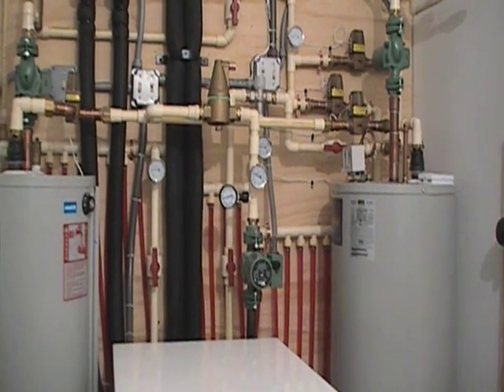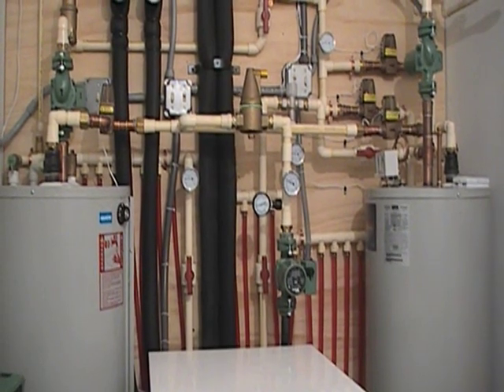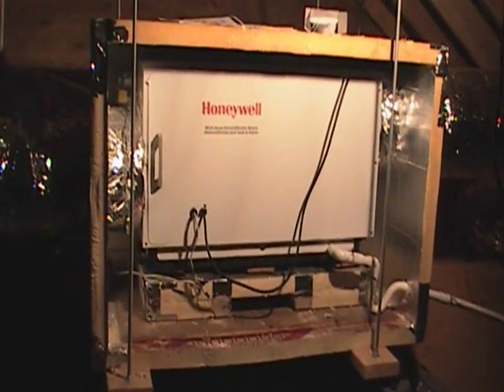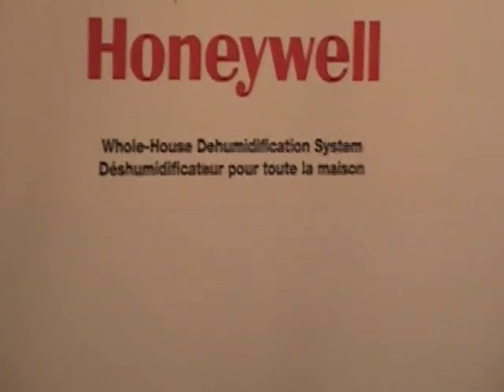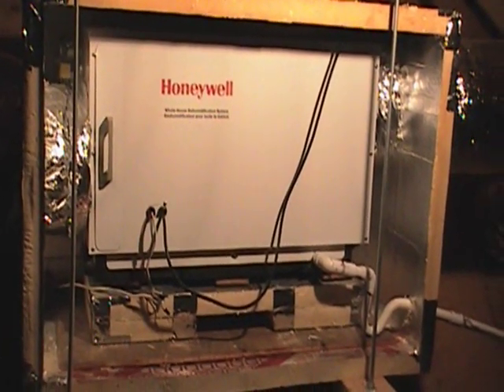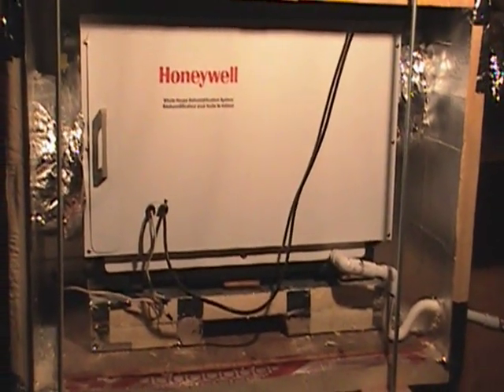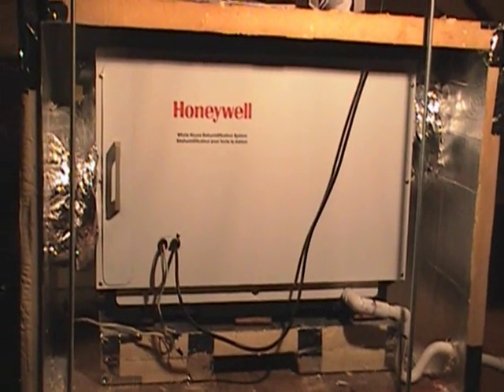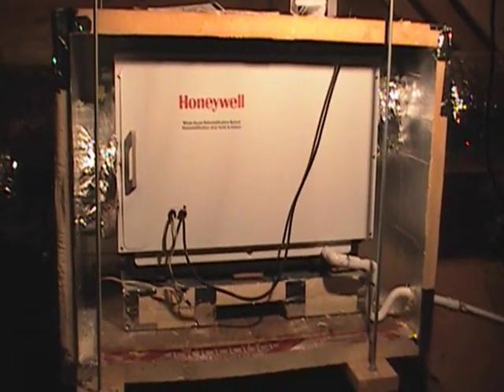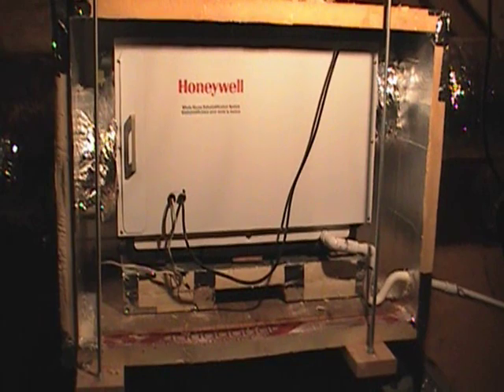Up in the attic, this is the dehumidification system — a Honeywell whole-house dehumidification system designed to remove as much as 90 pounds of water per day out of the house, hooked up to the dehumidification system downstairs. Especially when we're in cooling mode, we've got to maintain our dew points just below the water temperature coming through the floor so we don't get condensation issues. This was a feature that had to be added when doing the radiant cooling system to control humidity, otherwise condensation would build up on the floor when the dew point got too high.